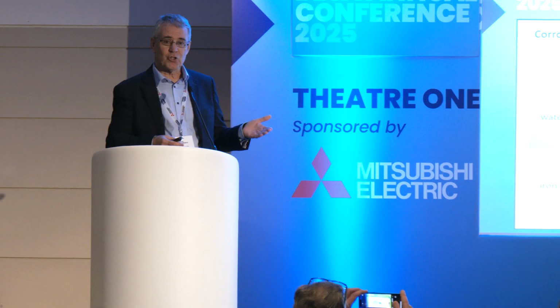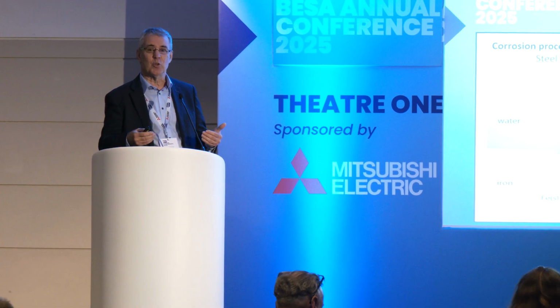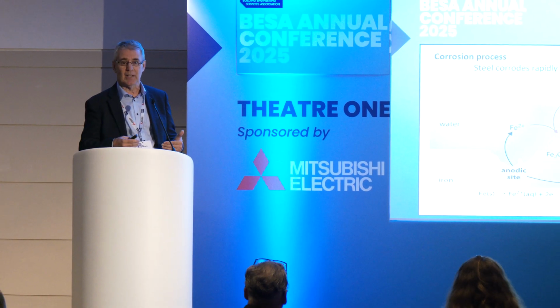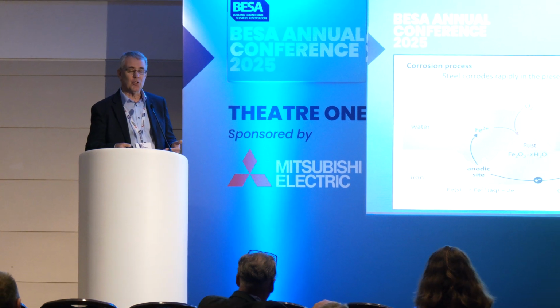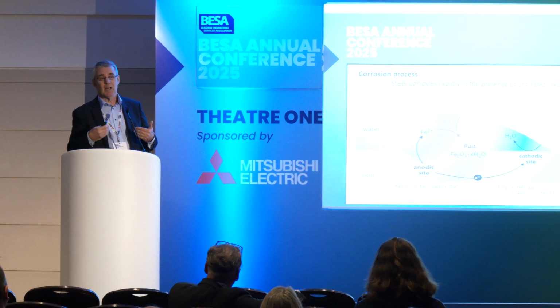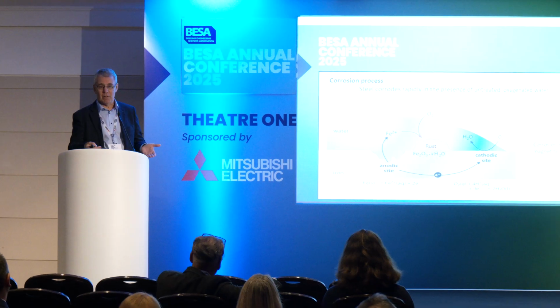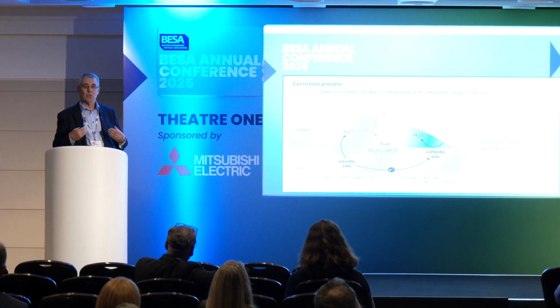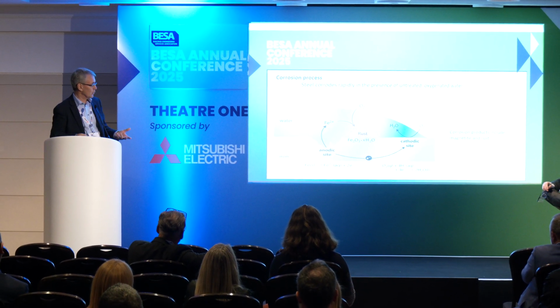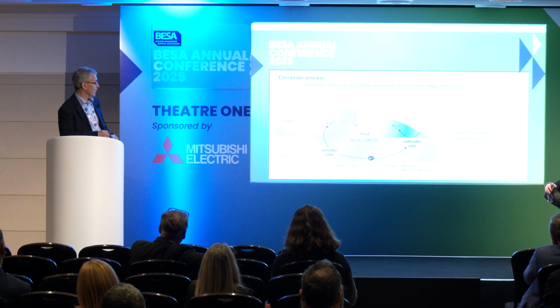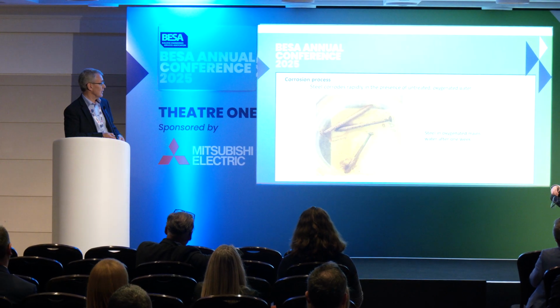So the corrosion process, we all should be pretty aware of it from our school days. It's the process where, in the presence of oxygen and water, steel will form a corrosion cell, which will drive corrosion. And the two main products of that corrosion are magnetite, which is the black sludgy stuff that you get in radiators, and also rust, the flaky brown stuff we're all familiar with. So that's the corrosion process.